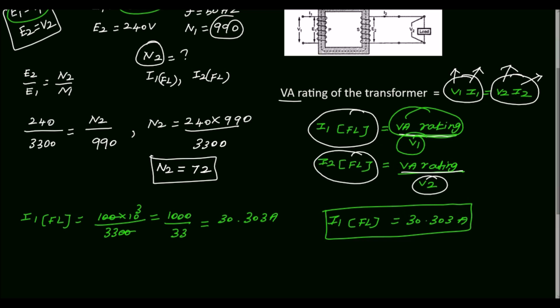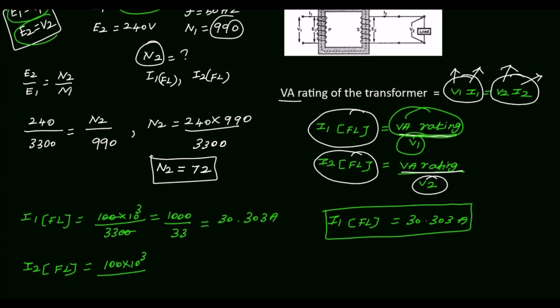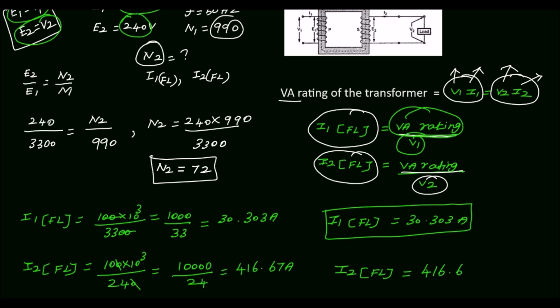Next, we will calculate the secondary full load current I2, which is equal to the VA rating divided by V2. The VA rating is 100 into 10 to the power 3. For an ideal transformer, E2 equals V2, which equals 240 volts. So I2 equals 100,000 divided by 240, which equals approximately 416.67 amperes. So the secondary full load current I2 is equal to 416.67 amperes.